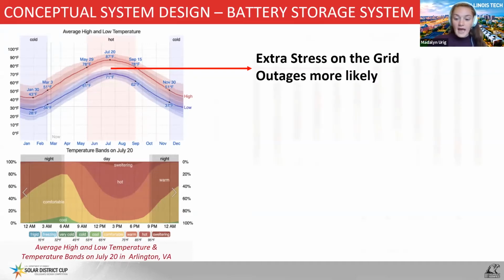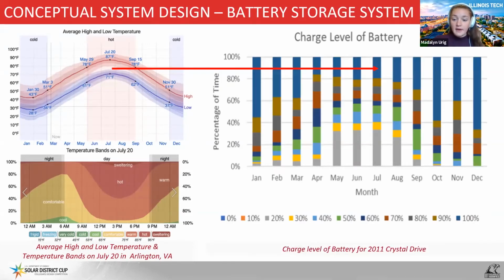Next, looking at the battery charge graphic, the battery spends a good portion of July in a depleted charge state. Our on-site batteries are used for peak shaving. The PV system only covers about 5% of the necessary electricity for the buildings.